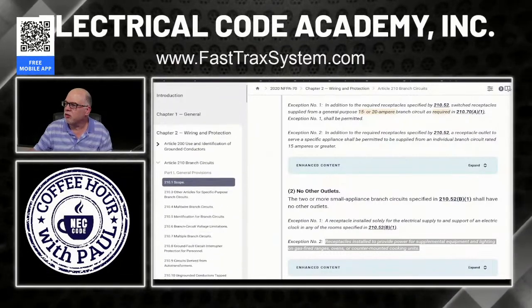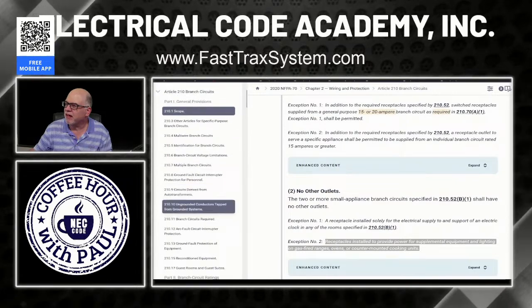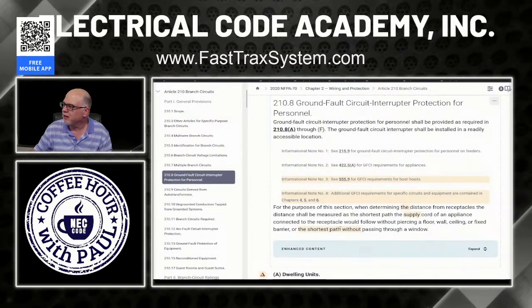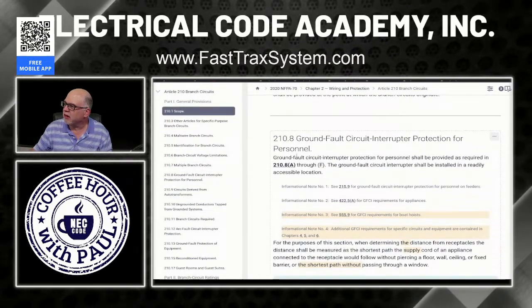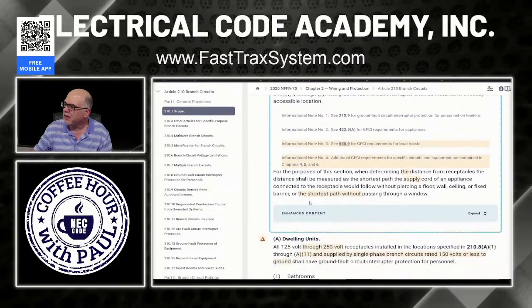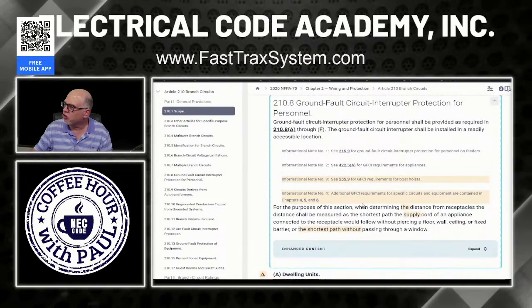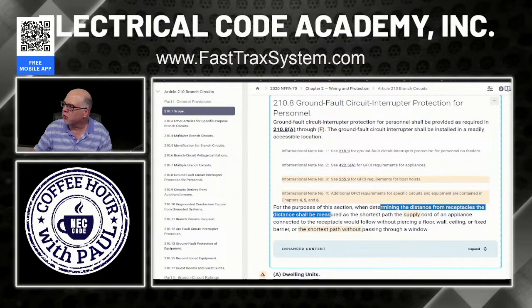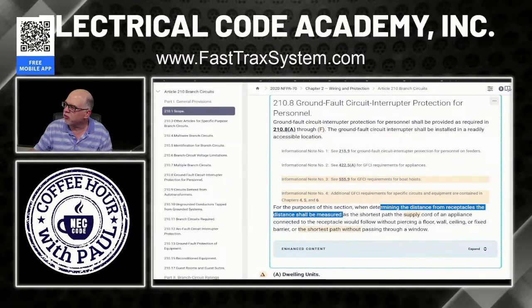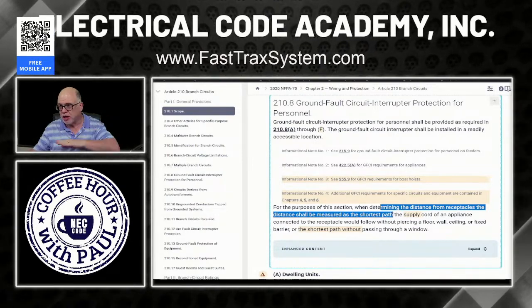All right, so let's go to 210.8 real quick. First time we've kind of dabbled in 210.8, by the way. All right, so see this right here, the ground fault circuit interrupter protection, 210.8. And we're talking about, for the purpose of this section, when determining the distance from receptacles, the distance shall be measured the shortest path. I mean, that means straight line, folks, not measuring the contours.